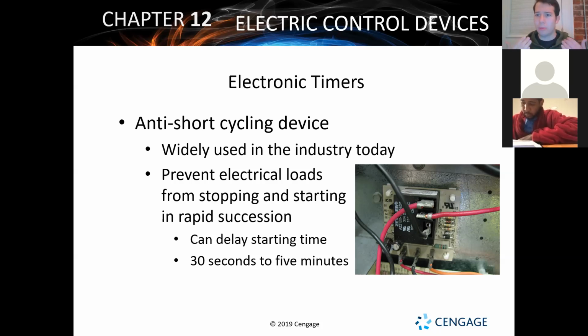Older systems would have only a couple of controls to stop a compressor from coming on. Typically, one control was to make sure that the compressor didn't overdraw amperage, and the other was to make sure that the compressor didn't over-pressurize the refrigerant system. If it overdraws on amperage, it just waits for the wiring to cool down, and then it fires on again. That could take a matter of minutes, or just a couple of seconds. But once it cools off, it'll fire right up again. So it'll shut off and then fire again. It just keeps starting up every 6 to 10 seconds.